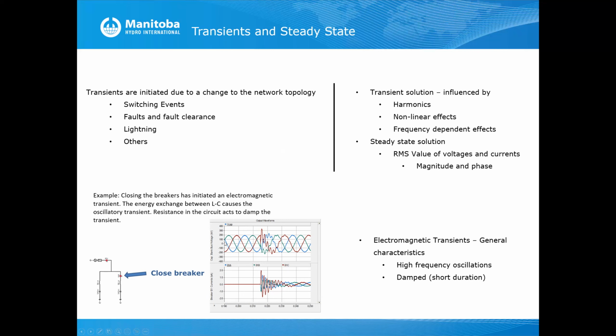Now, in steady state, when everything is operational and fine, the waveforms show a three-phase perfect sinusoidal wave. How do you get these high frequency components superimposed on your fundamental? It's when any of the following can happen: a switching event, faults in your system, lightning, or other events, meaning the topology of your system has changed, such as this.